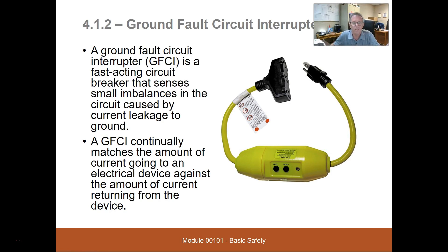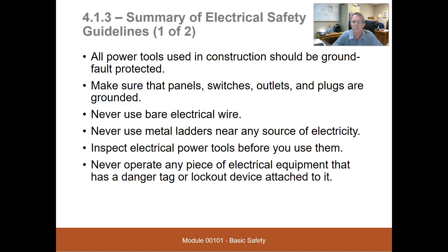You can also get GFCI protection with a GFCI circuit breaker or a GFCI receptacle. The GFCI is a fast-acting circuit breaker that senses small imbalances caused by current leaking to ground. It continually monitors the amount of current going to an electrical device against the amount of current returning from the device. All power tools used in construction should be ground fault protected.